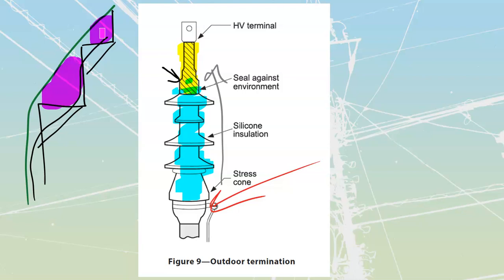Be very careful. They give you a note about mechanical damage caused by careless handling and installation methods. Poor terminations are the second biggest cause of cable failure. So usually, if there's a failure, it's because the cable got damaged during the install, but if not, it's usually the termination.